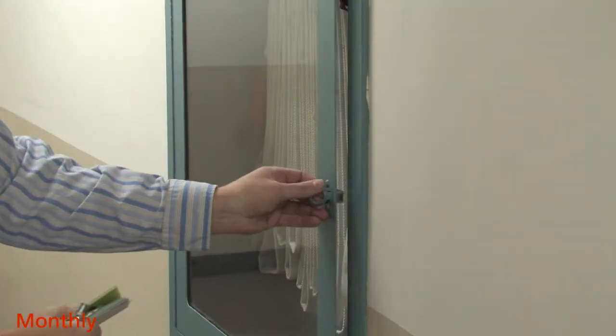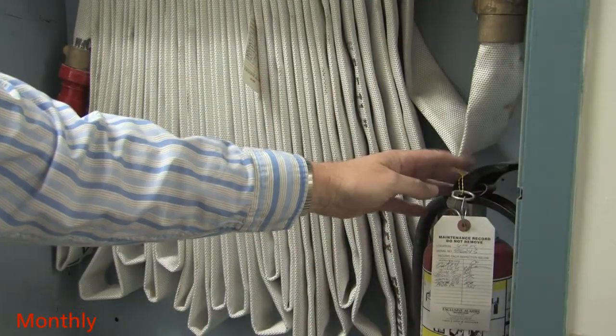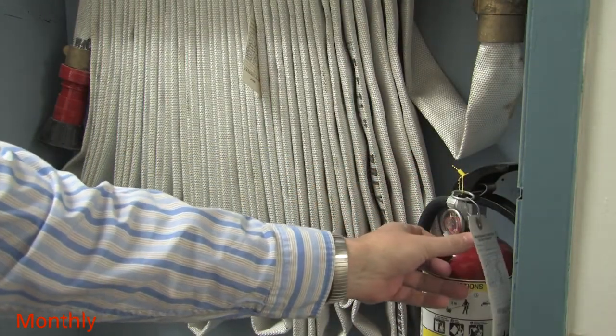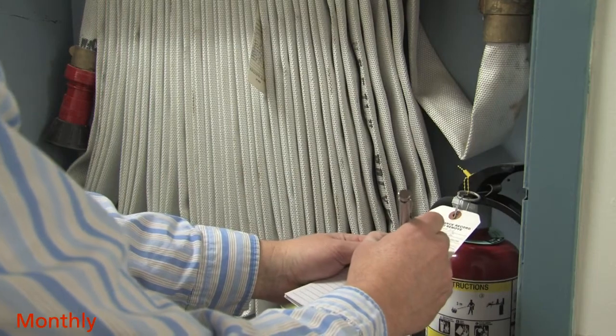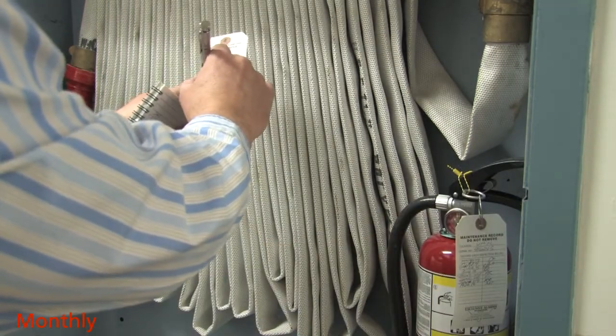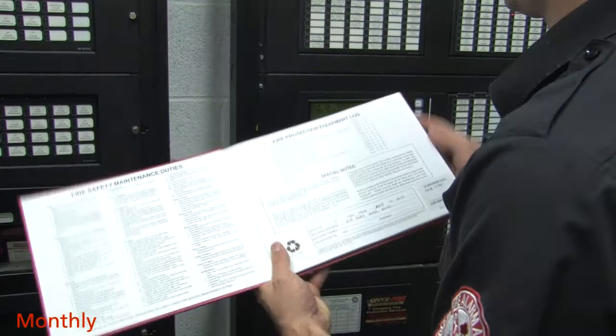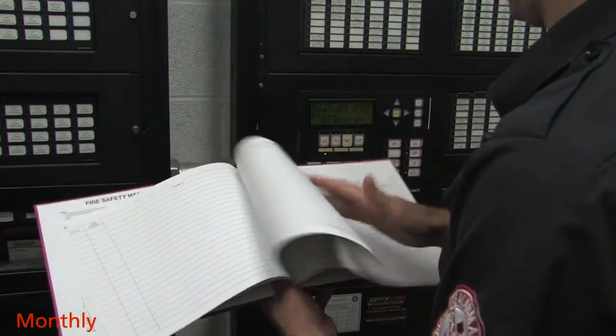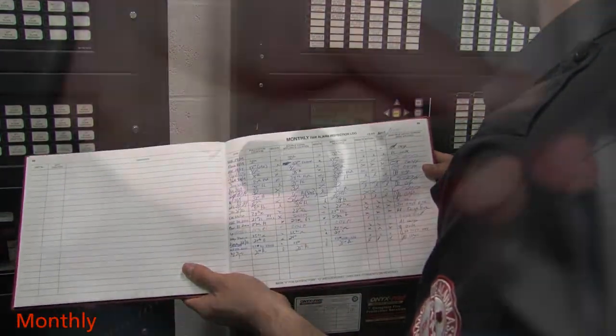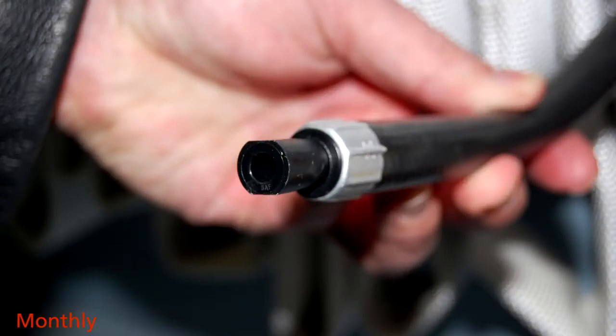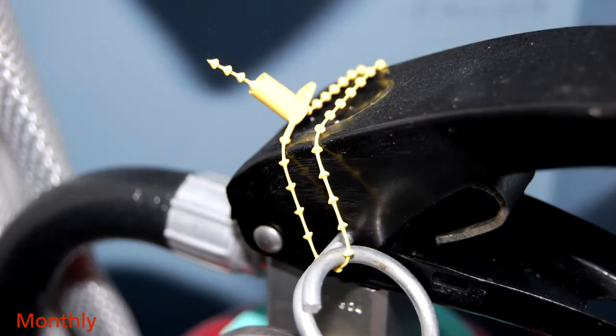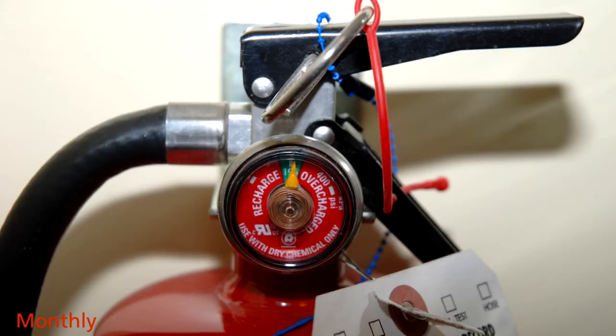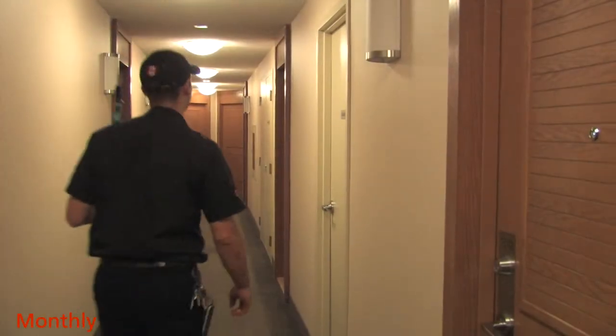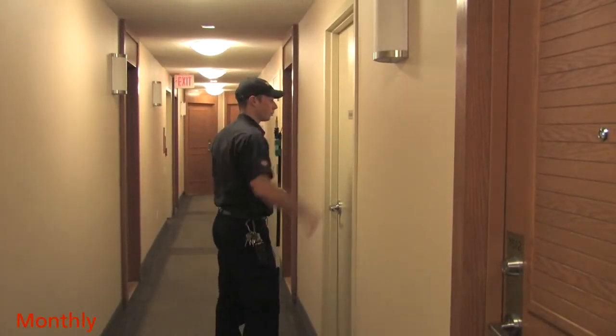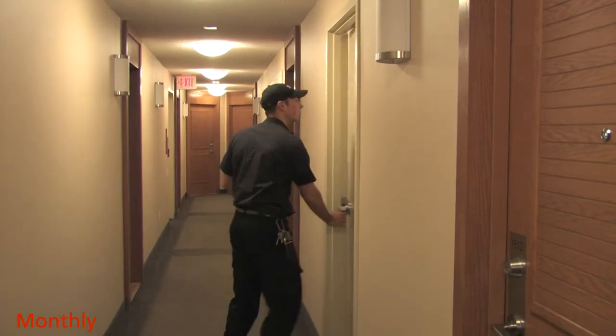Also on a monthly basis, site staff should inspect all portable fire extinguishers and record the inspection date and their initials on the extinguisher tag. This information must be recorded in the building's fire log book. Staff should check the following elements of each fire extinguisher. Check extinguisher nozzles for any obstructions. Check that the tamper seal is in place and check if the recharge gauge is showing an operable range. Site staff should report any defects. Any repair or recharge must be done by a qualified fire protection contractor.